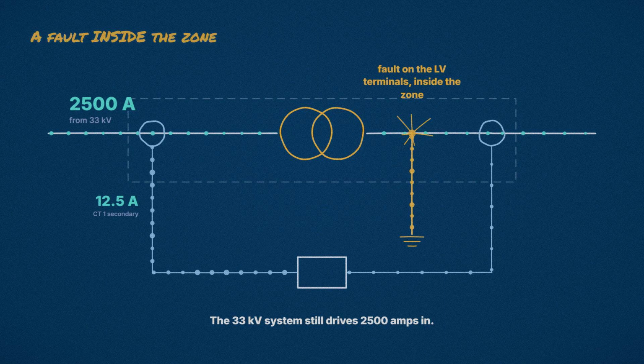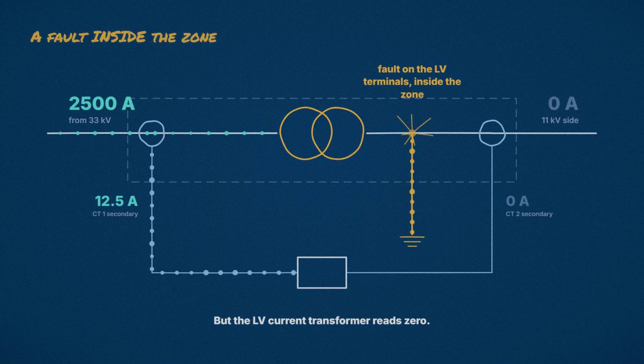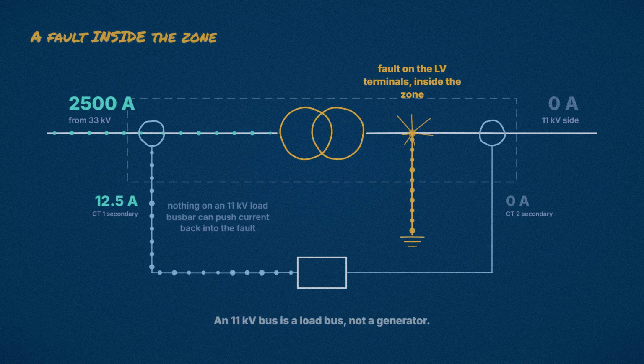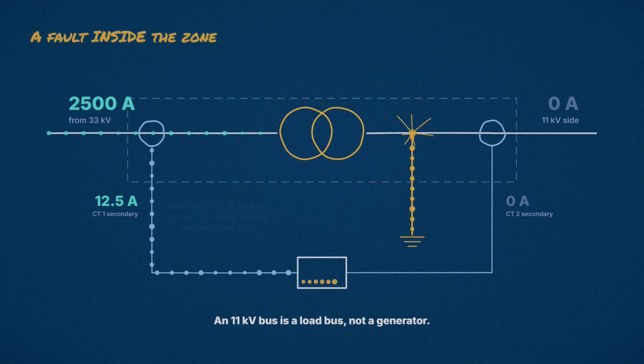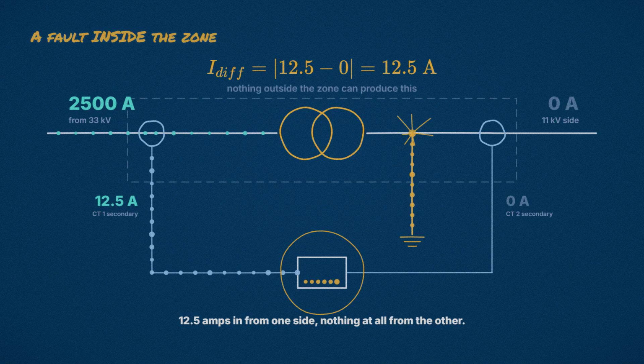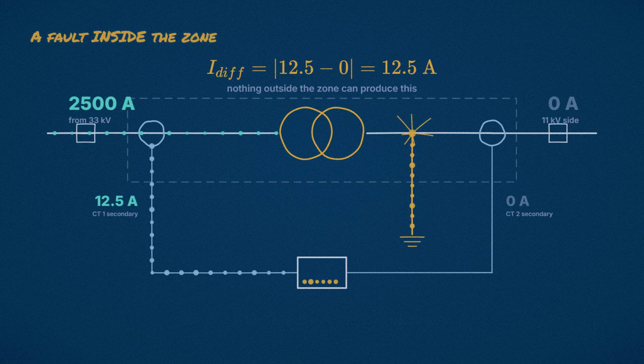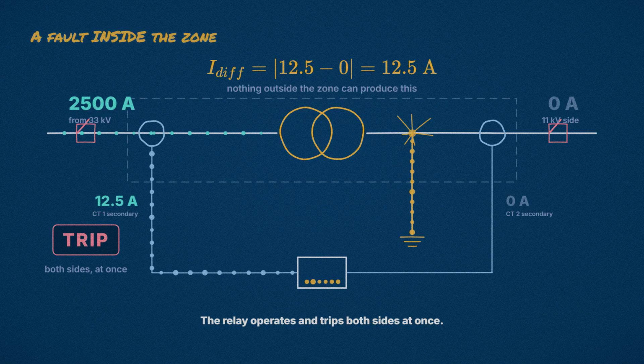But look at the low voltage current transformer. It reads 0. There is nothing on the 11 kilovolt bus bar to push current back into the fault. It is a load bus bar, not a generator. So the relay sees 12.5 amps arriving from one side and nothing at all from the other. 12.5 amps of differential current, where a moment ago there was none. Nothing outside the zone can produce that, because anything outside flows in one end and out the other. The relay operates and it trips the breakers on both sides at once.